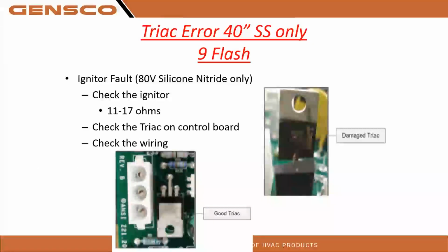Okay. So on the 40-inch furnace, we're going to get a 9 flash, right? So igniter fault, this is 80 volt. So we're going to check the igniter, 11 to 17 ohms. There also is a triac in the control board. So you can see the picture of that good triac on the left, and on the right, you can see the picture of the damaged triac. So it could be something on the control board in the 9-flash 40-inch furnace market.